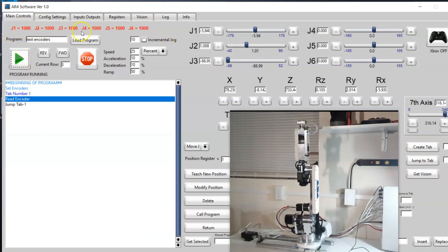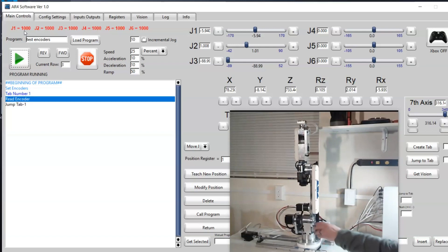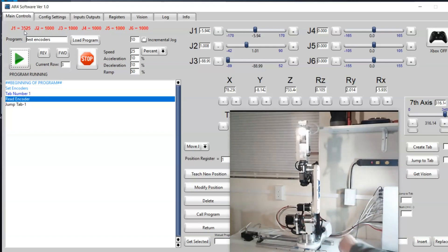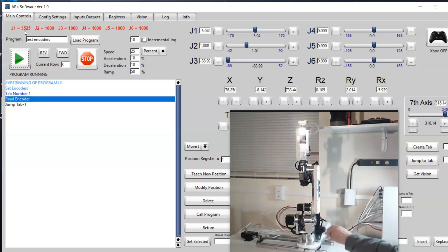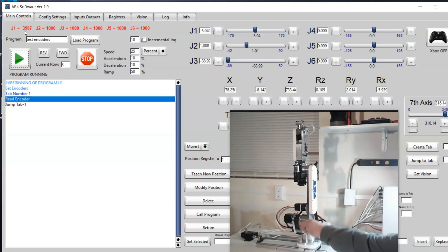These are just arbitrary numbers. I started at a thousand. The number doesn't mean anything, but it's just meant to give you an indication for each joint that the encoder's responding properly. For example, if I manually manipulate joint one you can see the value climbs in the positive direction, and if I manually manipulate it the other way you can see it goes in the negative direction.